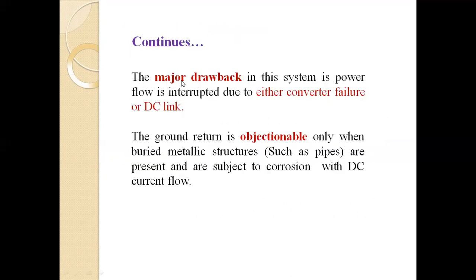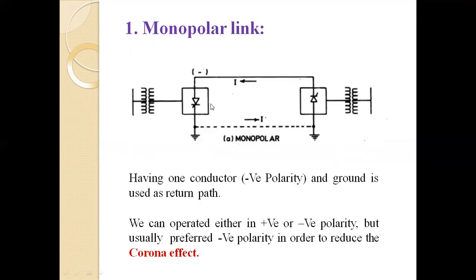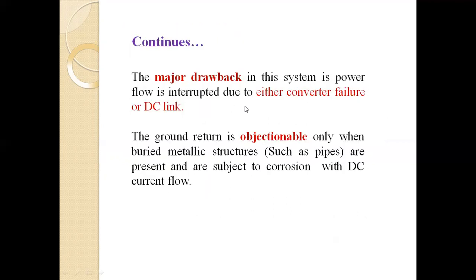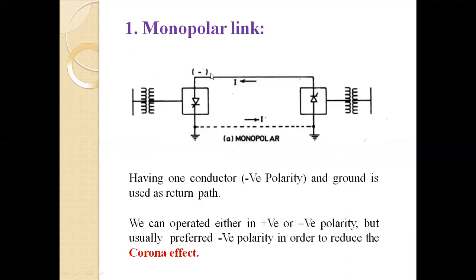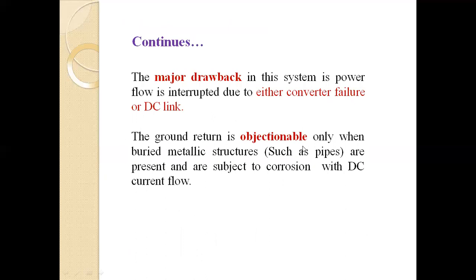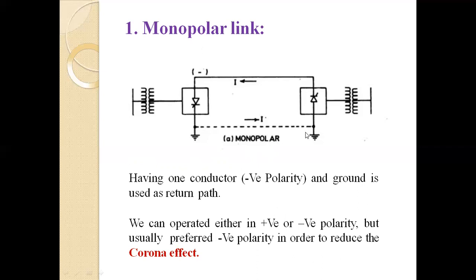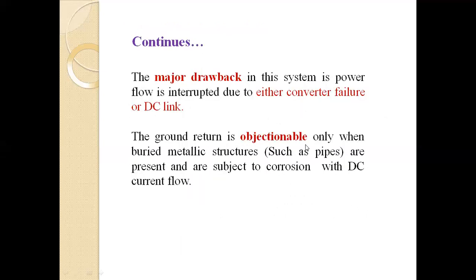The major drawback in this system is that the power flow is interrupted due to either converter failure or DC link failure. If the conductor breaks down, then the power is not flowing through the transmission line, or if any converter has any problem or maintenance issue, then the power does not flow through this link. The ground return is objectionable only when buried metallic structures, such as pipes, are present and are subject to corrosion with the DC current flow. So when a metallic structure is there, at that time the ground return is an objectionable part.